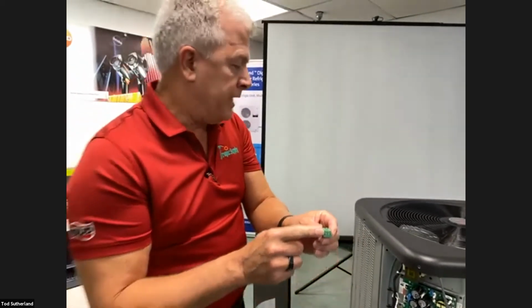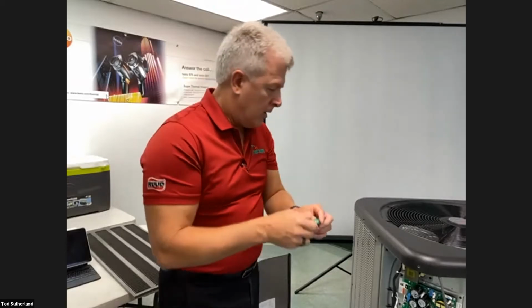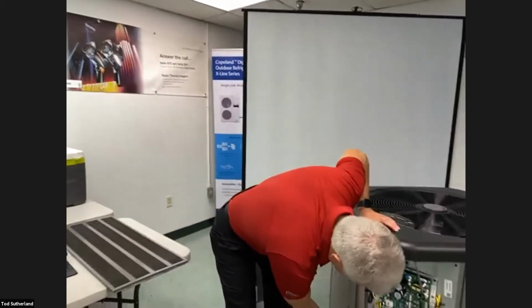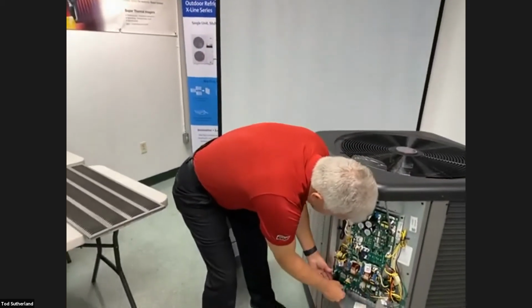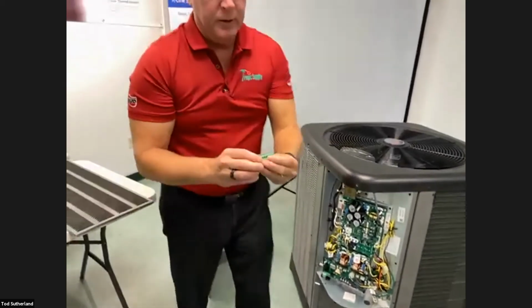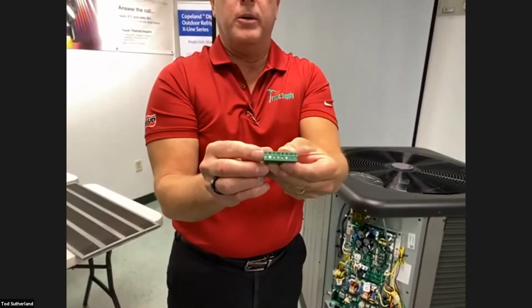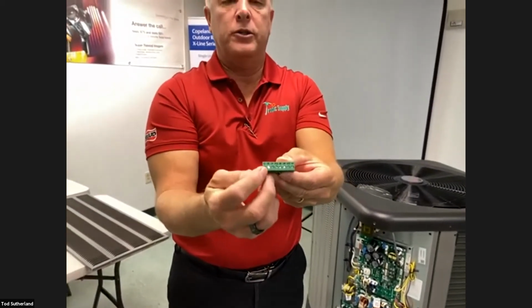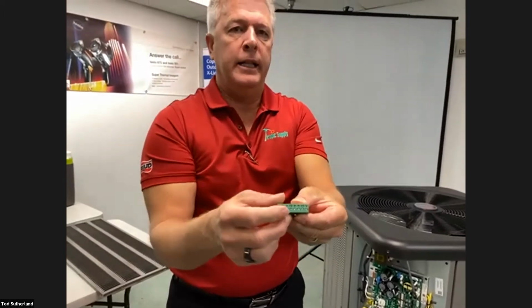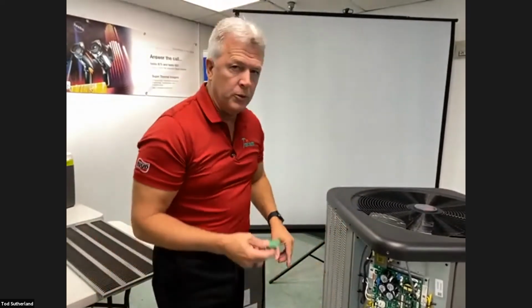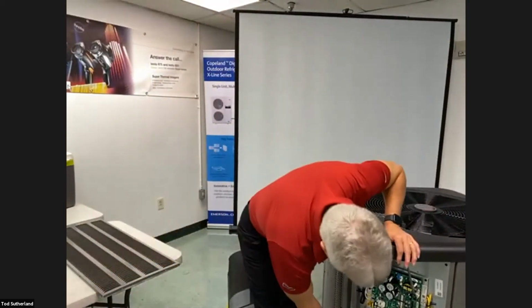Okay, that's for when you're using shielded wire, and that's where you would terminate the shielded wire for R if you're using shielded wire. On the other plug that we have down here, this is where you're going to have your common and your R terminal. So you're going to use those 2 on there, and then you're going to use the E1 and the E2 that's on the board there.